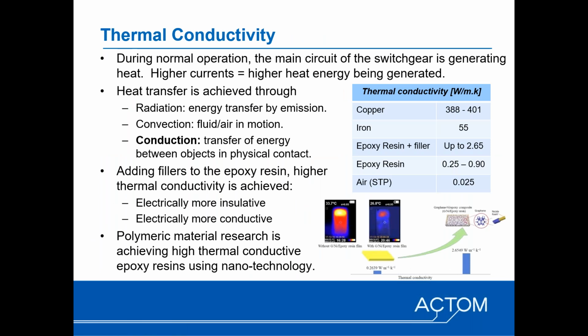One of the other components, and Narek touched on this, is the thermal conductivity of the epoxy. Not only does it need to deal with the electrical stress, you also need to deal with the thermal stress of the material. During normal currents, the higher the currents, the more heat is being generated, and the epoxy needs to be able to get rid of that heat in order to still maintain the rated current. Heat transfer can be done as a combination of 3 methods. The first one is radiation, where the heat energy transfer is done by emission. Convection, where airflow or fluid flow in motion is basically getting rid of the heat energy.